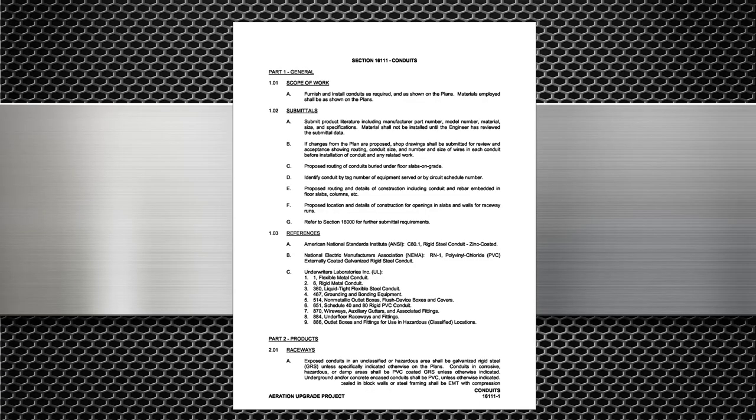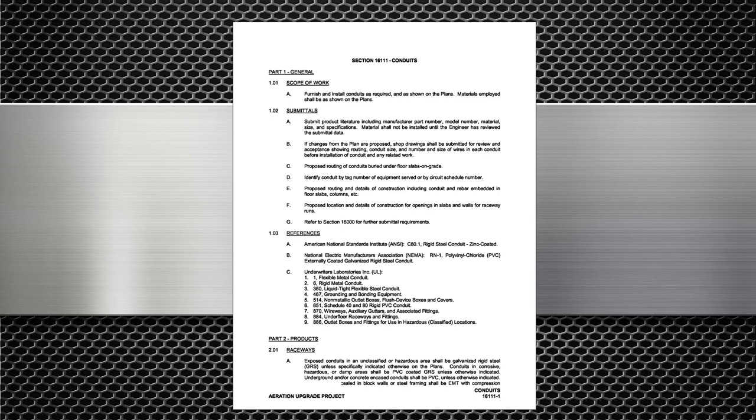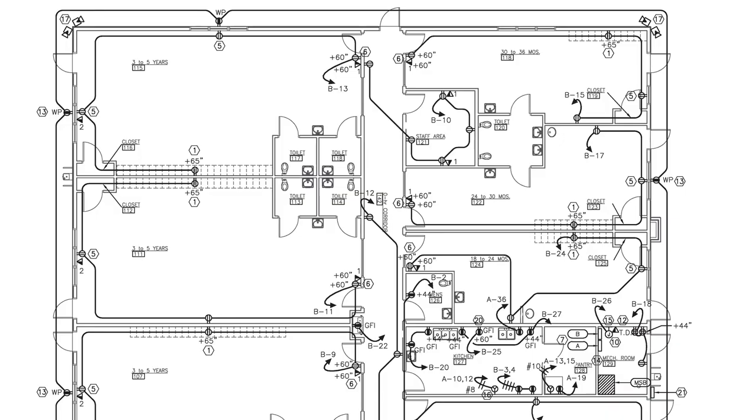Depending on the size of your project it may include a specifications book or it might simply list the specifications on one sheet of the drawings. Either way you need to read the specifications prior to completing your takeoff so that you know what type of materials and applications you can use. If there is a spec book you'll find the electrical specifications in division 16 or section 16000. For our purposes here we're going to assume that our project does not include the use of MC cable concealed in walls meaning we can use it above t-bar ceilings but we'll have to use EMT in the walls. We're going to assume that we're dealing with a three-phase system and that the specifications permit us to group circuits with one neutral for receptacle loads but require separate neutrals for all lighting loads.